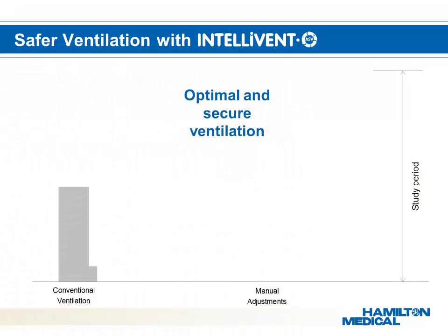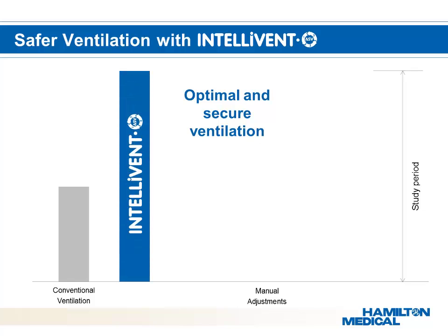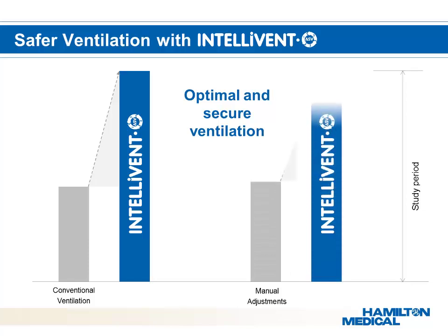IntelliVent ASV helps physicians reduce the potential for mistakes and errors. In a clinical study, patients with changing lung conditions spent more time within an optimal ventilation range using automatic IntelliVent ASV than patients in the manually controlled group with conventional ventilation. Prior to the study, acceptable and suboptimal zones of ventilation parameters — like tidal volume, SpO2, ETCO2, and inspiratory pressure — were determined.